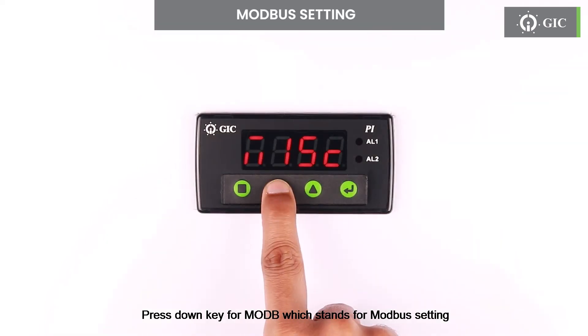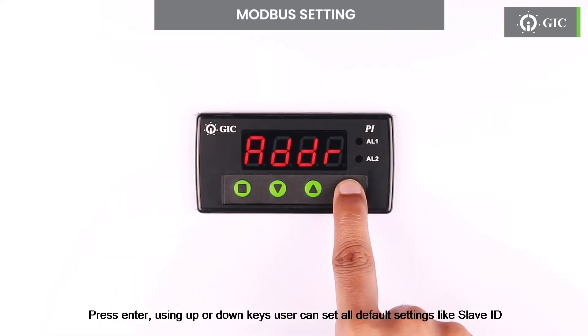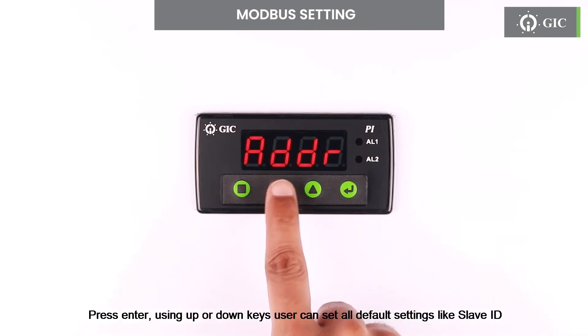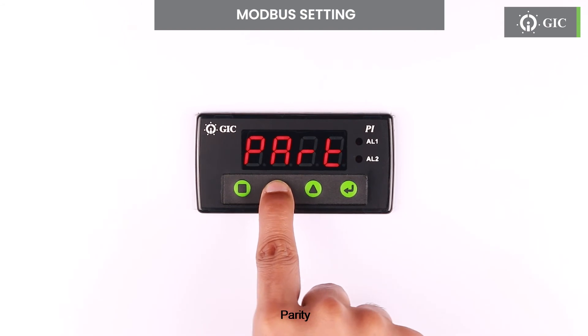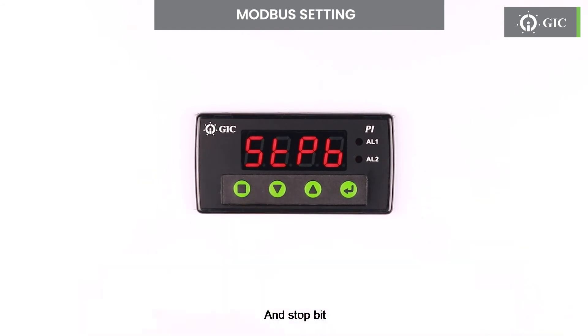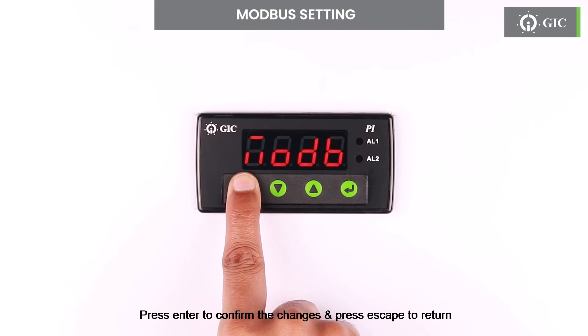Press down key for MODB, which stands for Modbus setting. Press enter, and using up or down keys, user can set all default settings like slave ID, baud rate, parity, and stop bit. Press enter to confirm the changes and press escape to return.